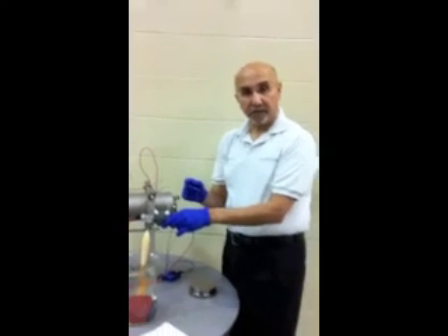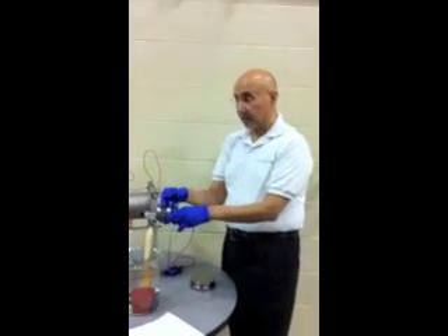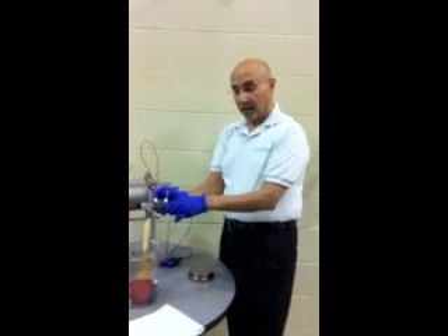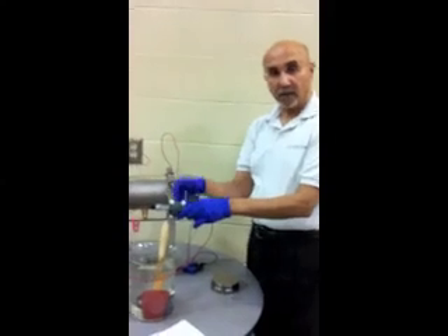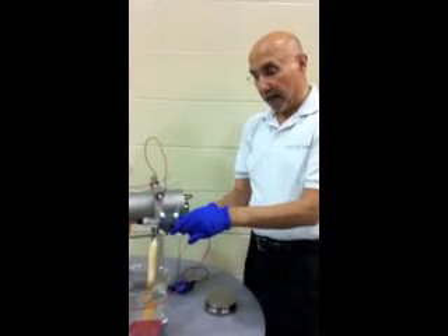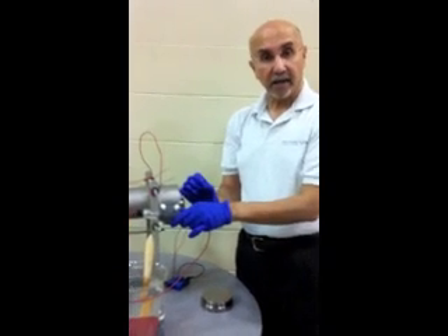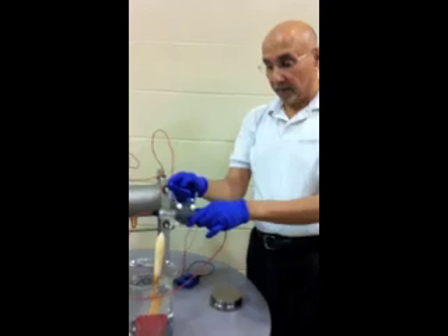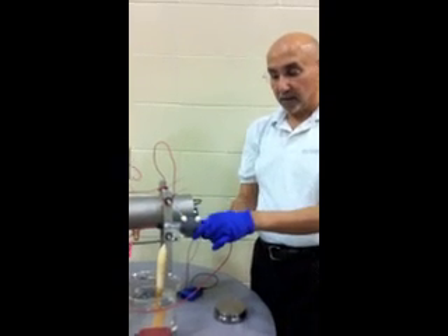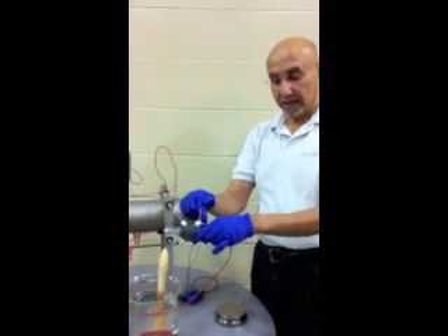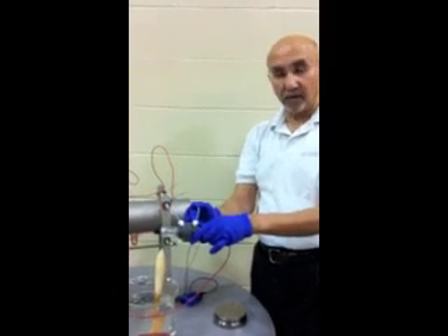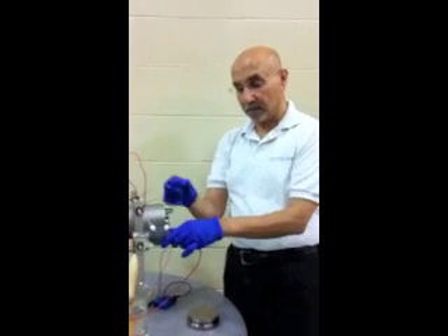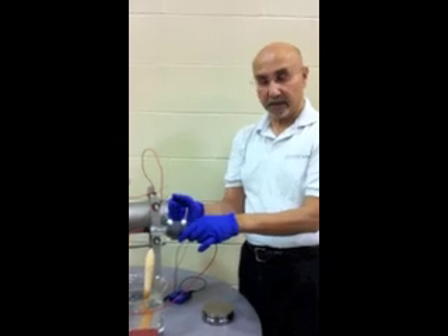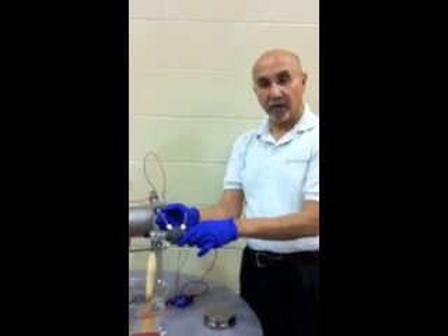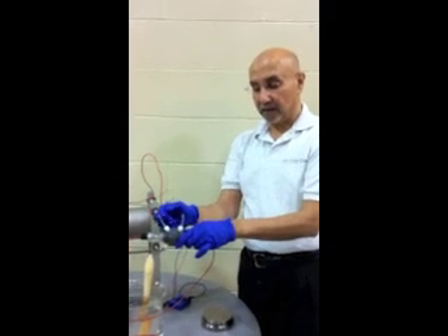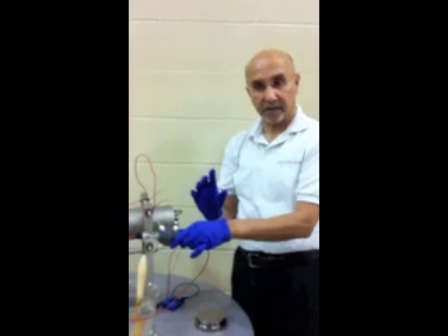Now, there are some modifications between the original device and this device. In the original, we had everything enclosed. In the current device, we have to allow some flow of seawater to respond to the changes. And this entails a bit of a design complication or sacrifice, because we need to enable seawater to flow in and out, but yet we don't want leakage current to go past the membrane and come back and corrupt our reading. And hence you have these tentacles that are little tubes that allow some ingress of seawater, but also provide a long current path so that you're actually restricting the amount of leakage current. This is the basic design sacrifice.